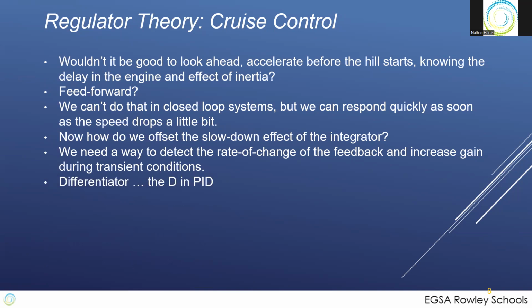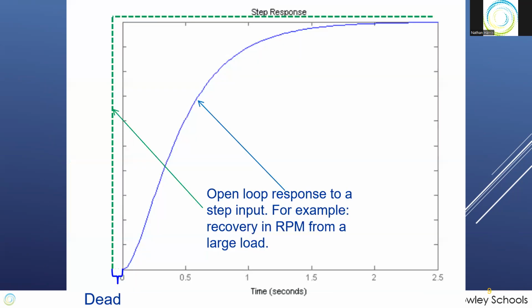So the D in the PID is rate of change. Okay, so think that proportional is gain, is response. Integral slows it down, and the differentiator comes in during rate of change. So it adds some gain during rate of change. So, a quick look, and this is a step response. Let's say we stepped up the input to a unit, and there was a slight deadband up front, but then we jump up and we respond to this input disturbance to the system. We add more fuel, we add more excitation boost if we need to.